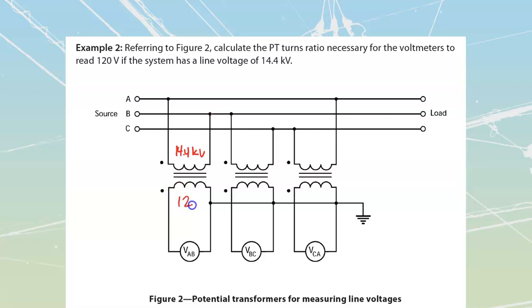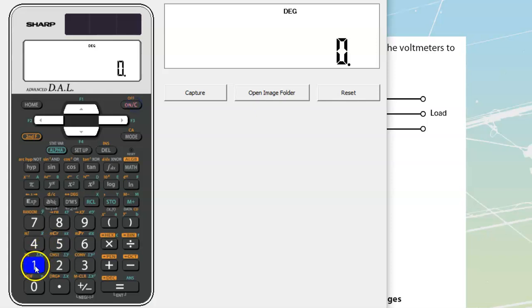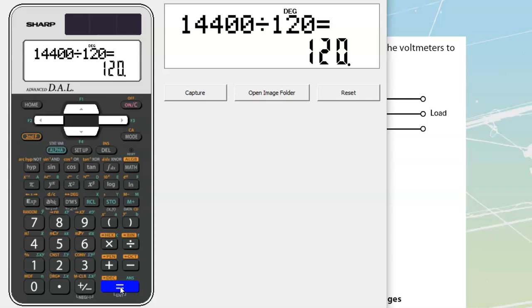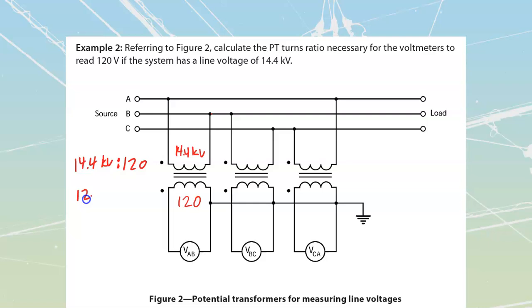And over here, this is going to be 120 volts, so really, if I was buying an instrument transformer, I would get one that is rated at 14.4 kV to 120. But since in this case they're asking for the turns ratio, it's relatively easy for us just to go 14.4 kV over top of 120 volts, which gets me to a value of 120. So we would need to have 120 to 1 rated transformers that are also rated for 14.4.